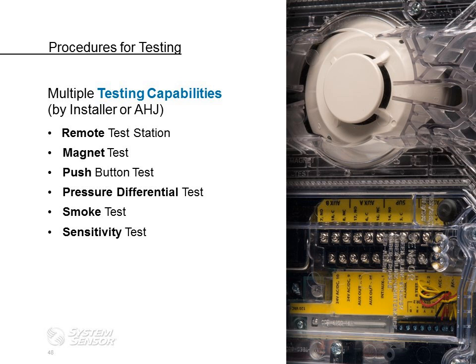Now, there are multiple testing capabilities built into the product, and these are performed by either an installer or an AHJ. There is the remote test station. There's a magnet test. There's a push button test. Obviously, a pressure differential test needs to be completed, a smoke test, and a sensitivity test.